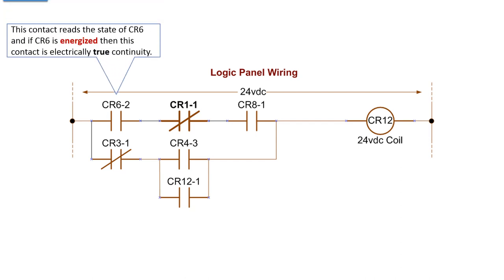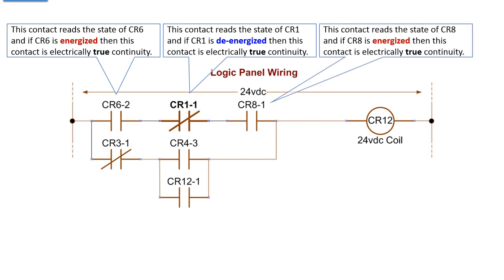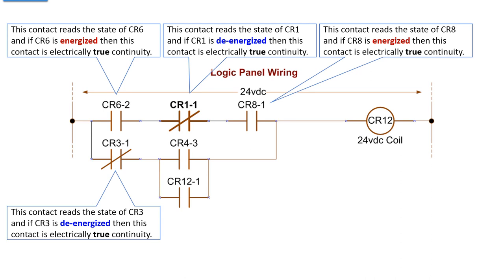This contact reads the state of the coil CR6, and if CR6 is energized, then this contact is electrically true continuity. This contact, which is a normally closed, reads the state of CR1, and if CR1 is de-energized, then this contact is electrically true continuity. If the coil is de-energized, true of on for the first one, true of off for the second. Third one's another true of on. This contact reads the state of CR8, and if CR8 is energized, then you have electrically true continuity. Consequently, same thing for CR3, if it's de-energized, then you have true continuity.